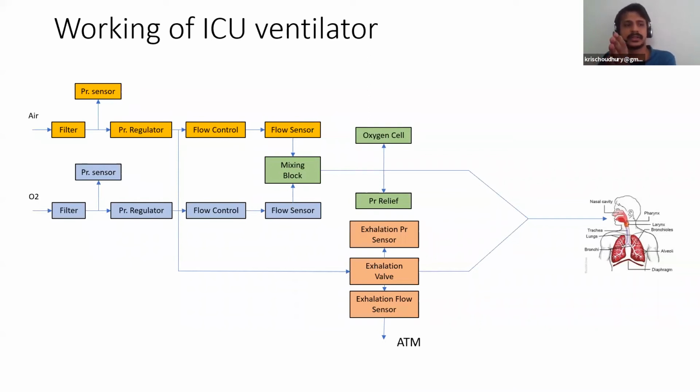As soon as the lung can overcome the pressure set by the doctor, this valve basically just leaks out, and it starts blocking once the pressure set by the doctor and the pressure in the patient's lungs are the same. You basically stop the breath.